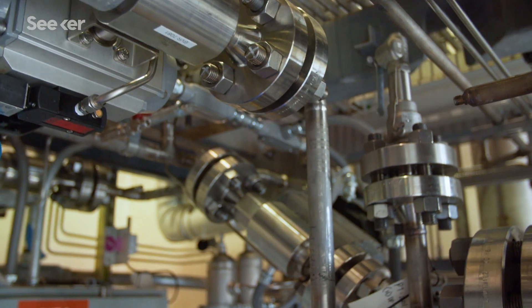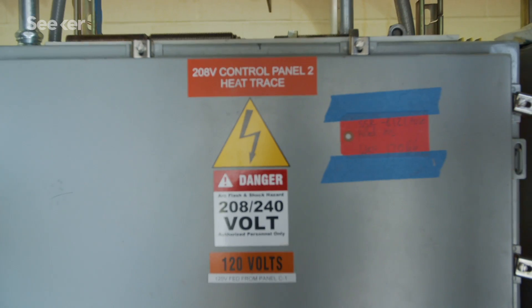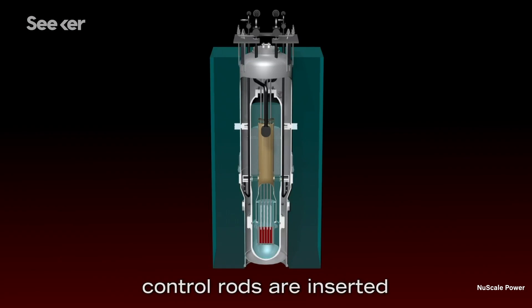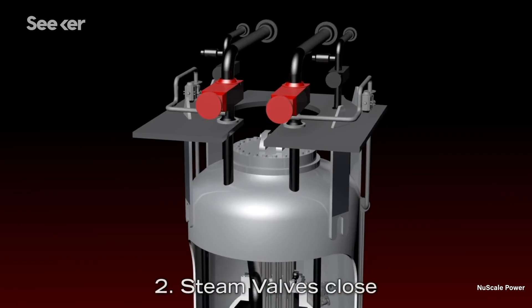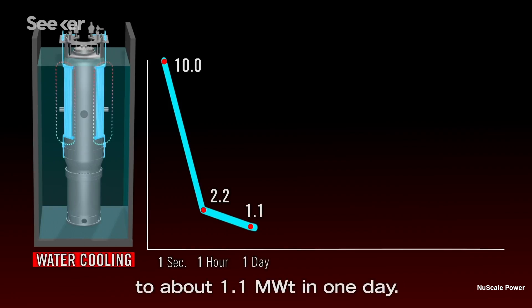There aren't any additional cooling pumps or generators that could fail in an emergency — a lesson learned from previous disasters. Passive safety describes the ability to perform a safety function without power. For NuScale's design, the reactors will safely shut themselves down without any operator action or computer action, without any AC or DC power, and they'll remain cooled for an indefinite period of time without the need to add water. When you lose power, the control rods fall into the reactor vessel into the core — they're held up normally by electromagnets, so you lose power, they disengage and fall. You go from 200 megawatts thermal to about 10 or 11 megawatts in a second or so.